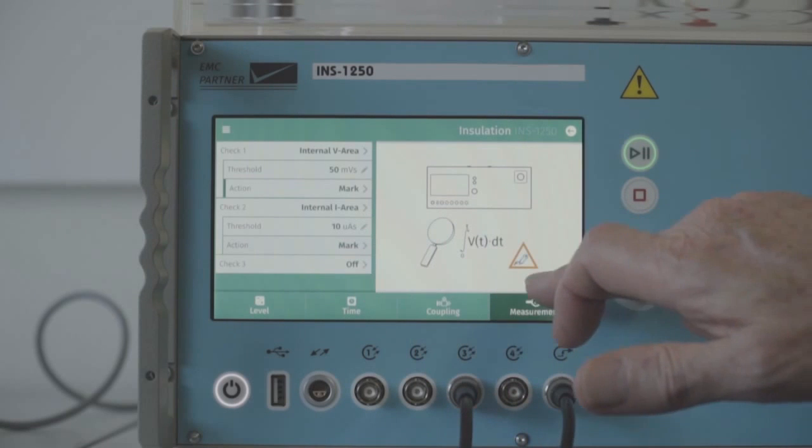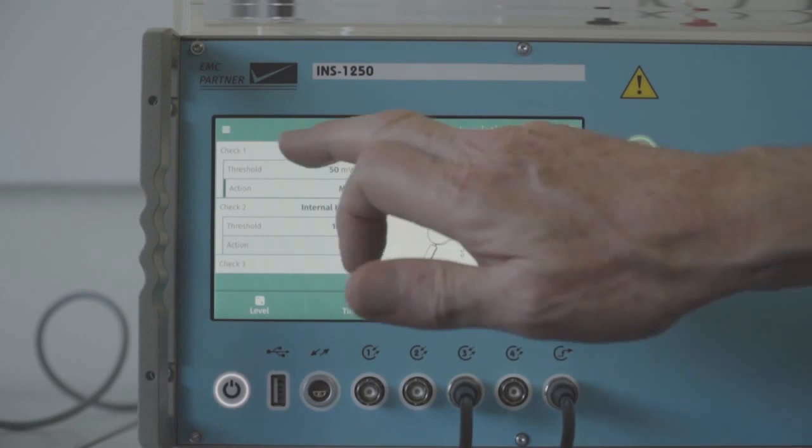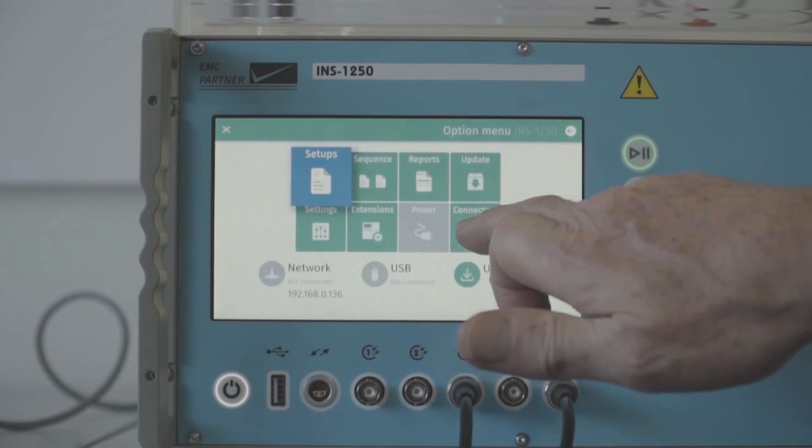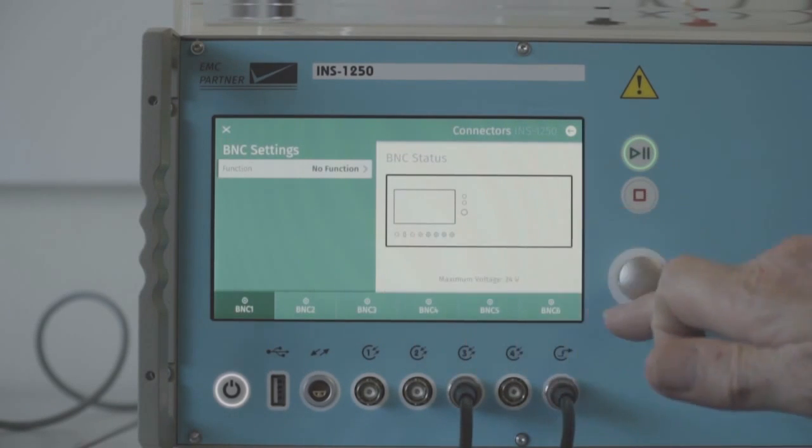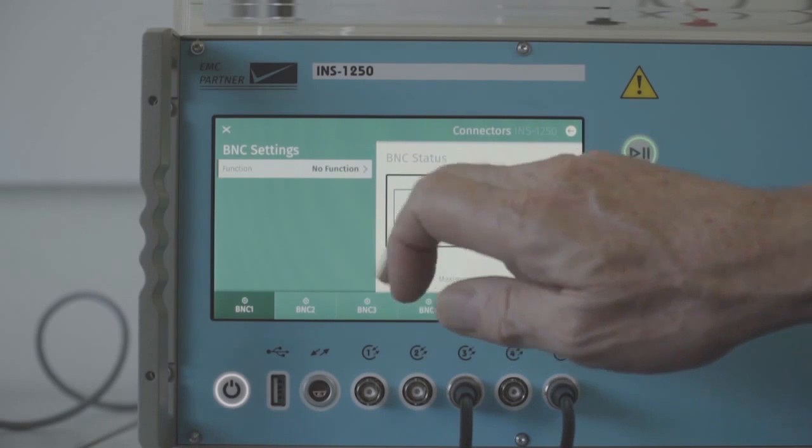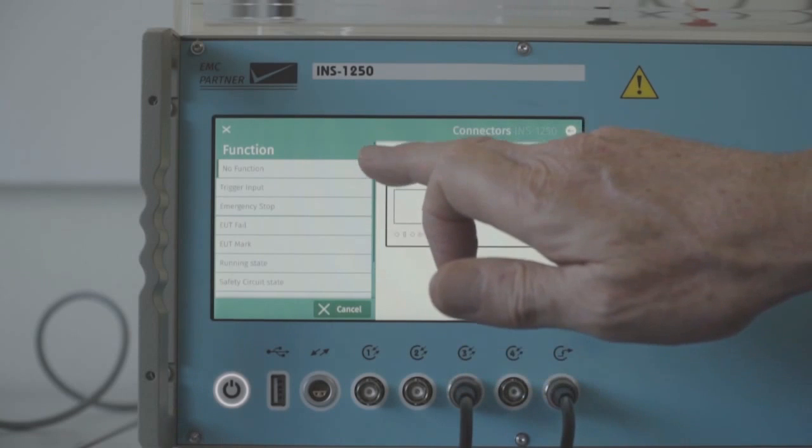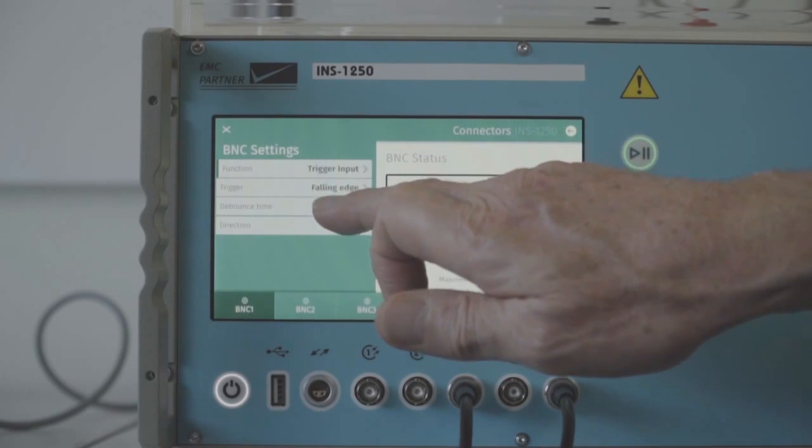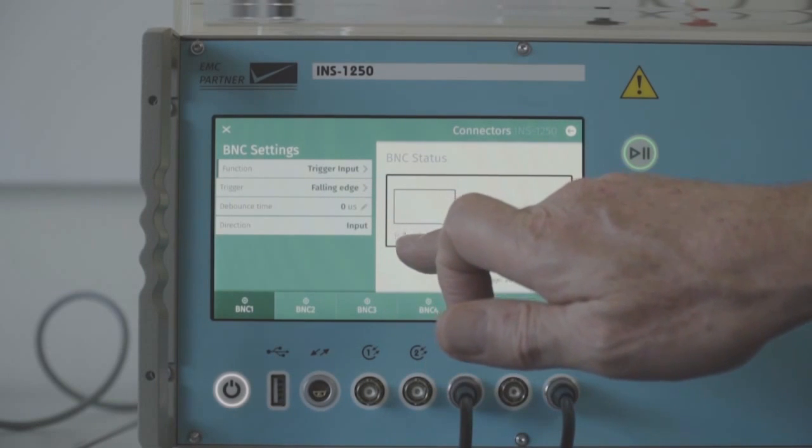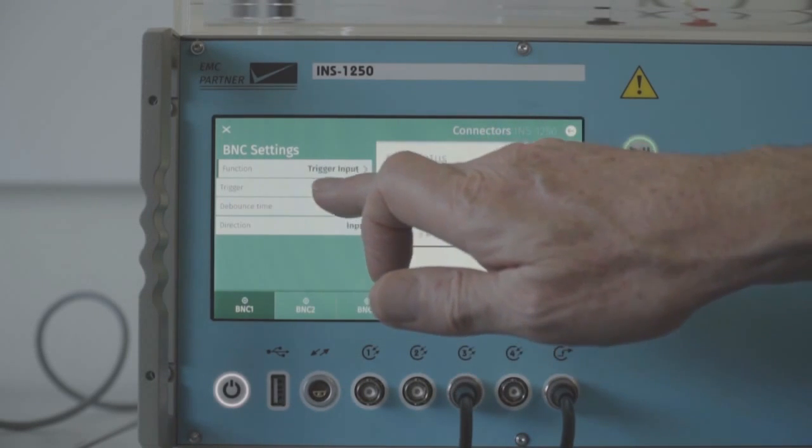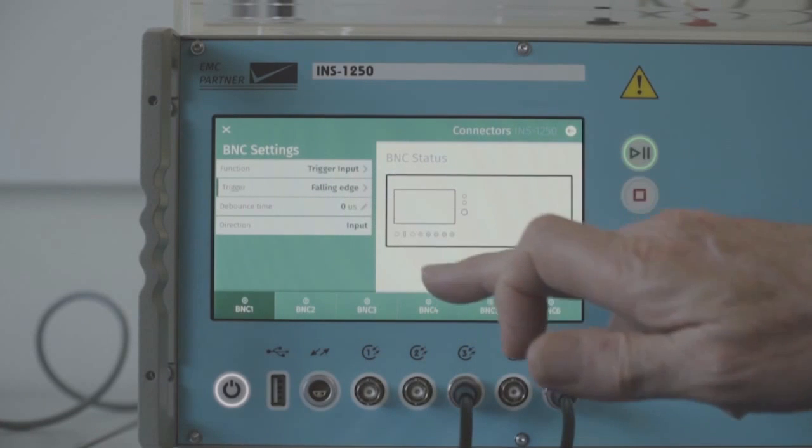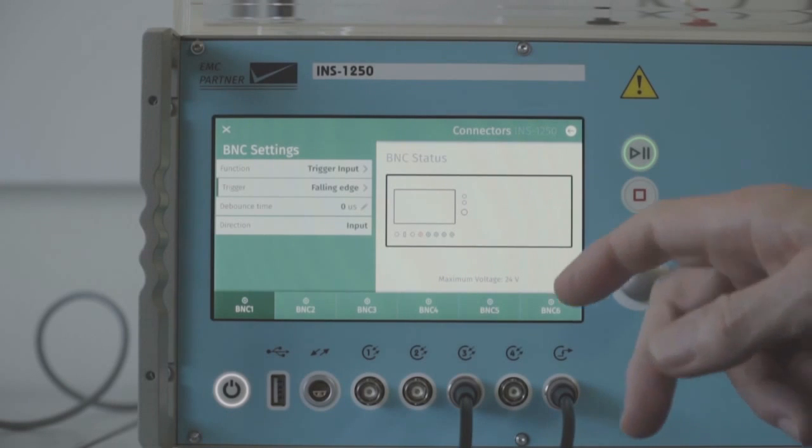We have three check functions that can be programmed during the test process. We can also program the BNC connectors on the generator. There are six connectors and these can be programmed with a multitude of functions. For example, we can have a trigger in function on one of the BNCs and we can change that to have either falling or rising edge. And a debounce time which ensures that if there is any interference on the signal you won't get a false trigger.